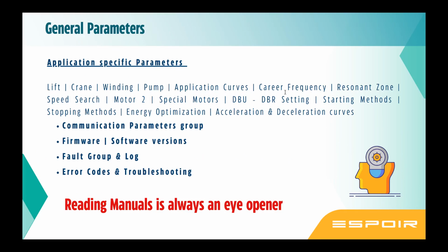Now when you stop at deceleration to stop, it will trip off on over voltage because you are trying to stop the motor before the inertia is over. It is going to pump back the voltage to the system and the drive will trip on over voltage. To fix that, two things: you have to increase the deceleration time, or you have to install a DBU and DBR.